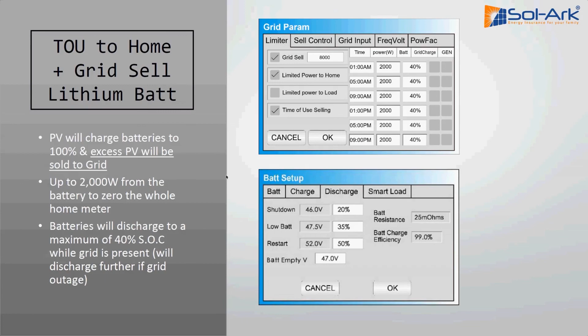Moving on, we've got smart load. Smart load is a cool feature. It's basically automatic load shedding. Inside the Sol-Ark 8K and the 12K, there are 3 breakers on the right. You've got the load breaker that just goes to your backup loads. Grid is the grid input, or generator input sometimes. And then the gen breaker is basically a Swiss Army knife breaker. We can program that to do quite a few things, and one of those things is smart load output. So we can only turn on the smart loads given you're making enough power on the solar panels or you have enough SOC on the battery bank.